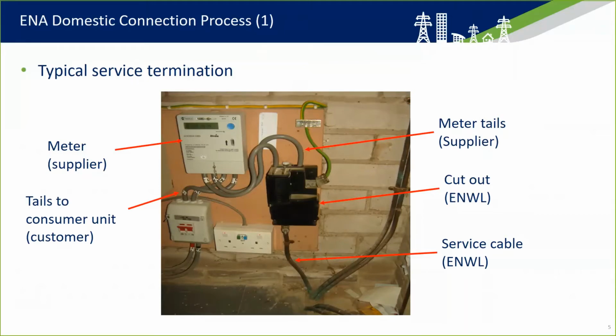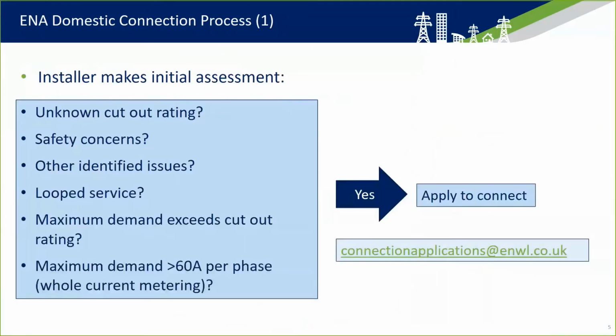Just one point to note, the installer must not remove the cutout fuse to identify its rating. That can only be done by ENWL or the supplier. So, a little bit more detail on some of the checks that need to be made. What's the rating of the cutout? As I said before, generally from the late 1960s, 1970s onwards, plastic cutouts came in with a rating of 100 amps or 80 amps, quite common, but older ones can be less than that. 40 amps, 30 amps are not that uncommon in older properties.